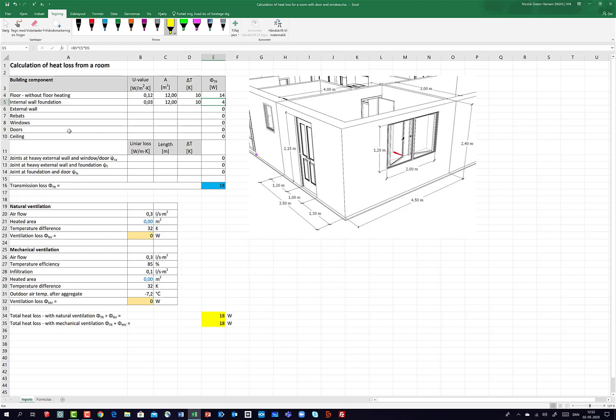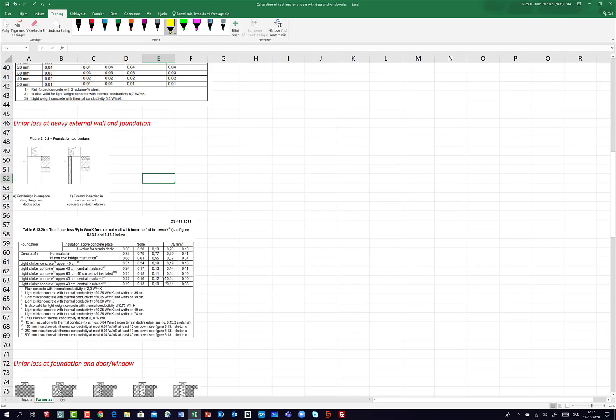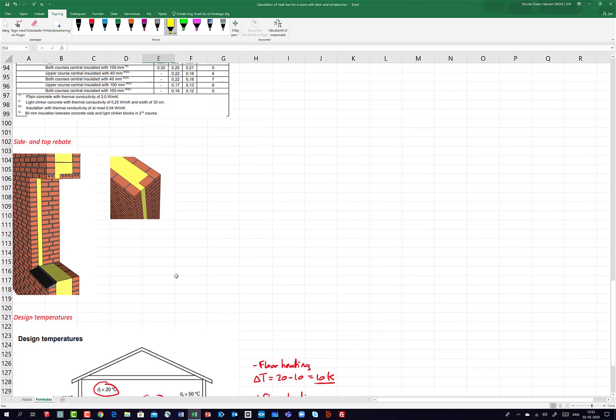Before I calculate the external wall, I'll take the rebates — the window and the door rebates. The rebate is shown in the formulas tab. In this example I have a side rebate, and I know the width of a brick is 108 mm. I also know that the U-value through the ordinary external wall is lower than through the rebate, which is why I need to take that into consideration.